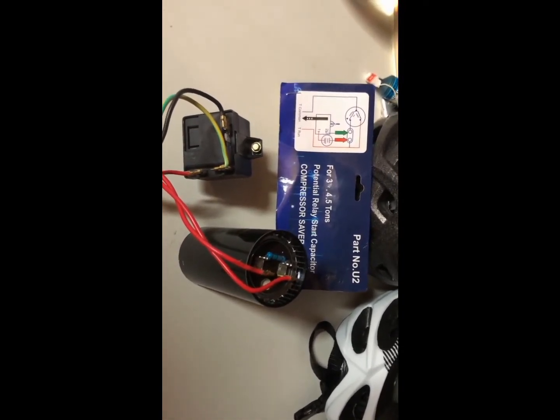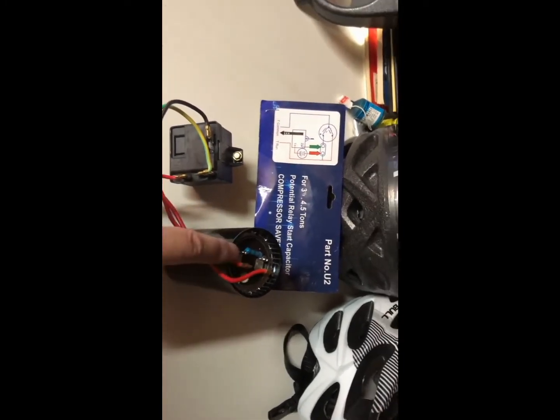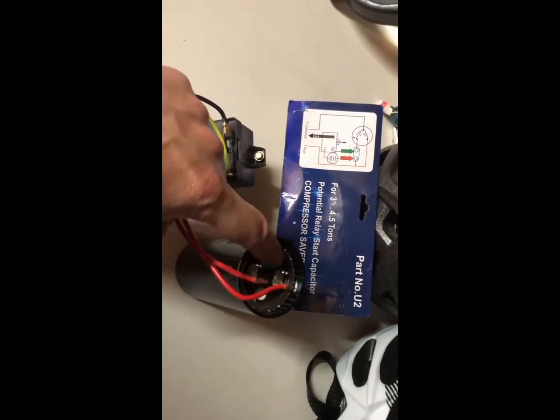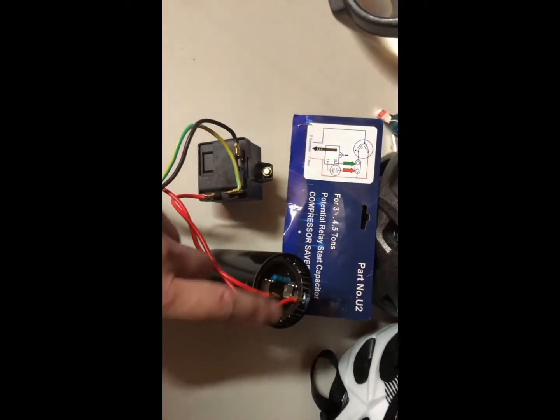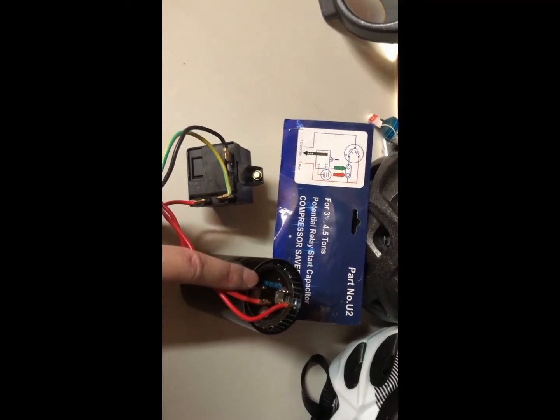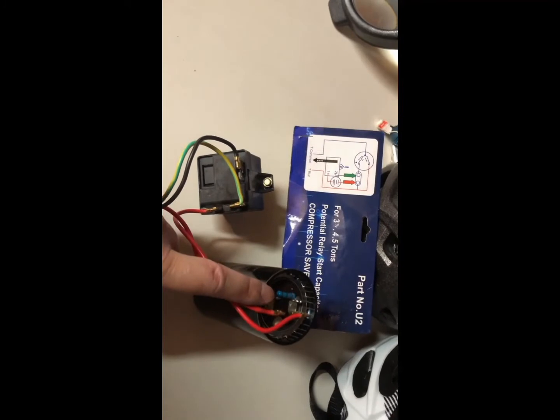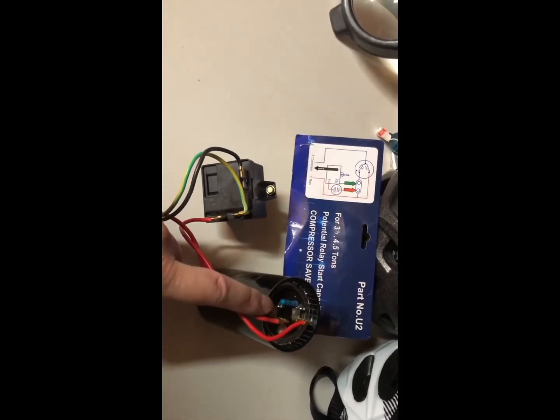It helps your compressor life last longer, and this cap here — every time your compressor stops, it has a resistor to discharge the voltage inside the capacitor. It also discharges the voltage inside your run capacitor, the one that you hook up to your compressor outside unit.